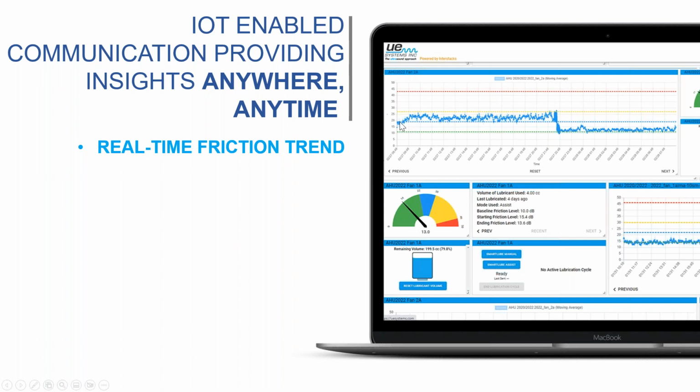The blue line is the needs lubrication. And what I can tell you is a lot of people start to think about it from a perspective of, well, can I narrow that blue line earlier? And you can, but I can tell you with confidence that the change in that decibel reading or friction level is so subtle, it's not doing secondary damage, right? So we have to balance between how often we're greasing and the level we're comfortable with rising before it greases. So that blue line is the needs lubrication. The yellow is a warning, and the red is a critical. And I'll walk through the ISO standards and how we set those.